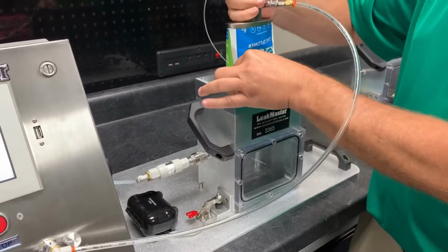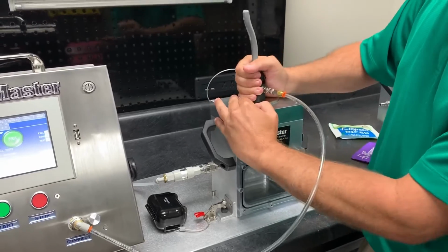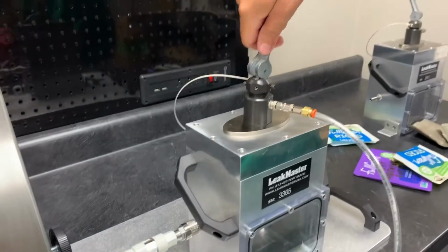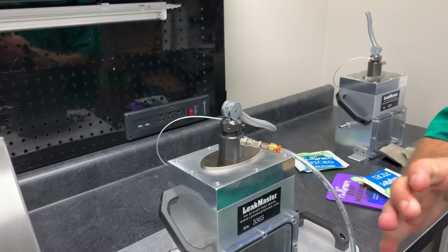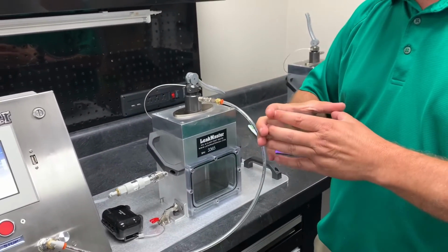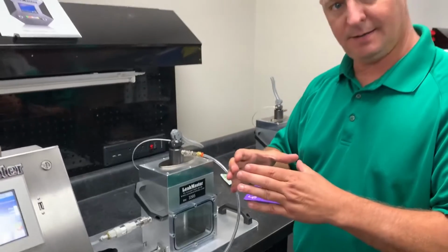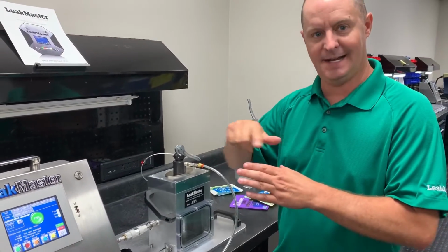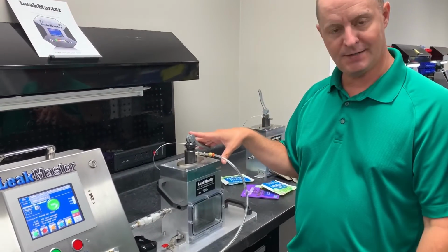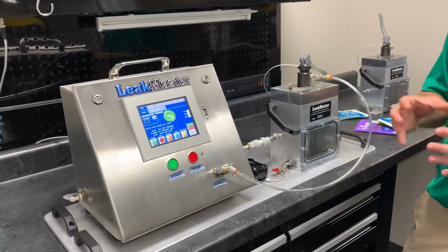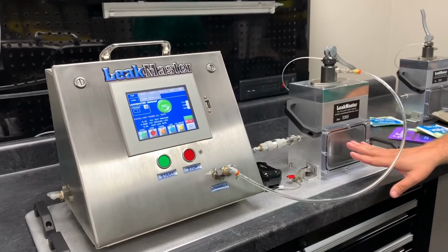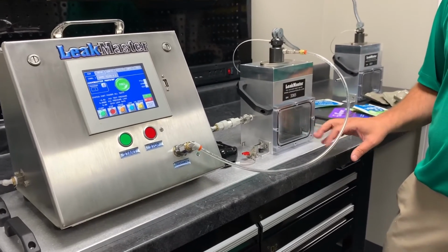So once we've got the part fixtured properly, this cam over seal is going to swell up that inside diameter and seal off the inside of the product while pressing it to the outside diameter seal. So at this point, it's ready to be tested. Now when I hit start, it's going to pressurize this bag. The bag's going to swell up. There's a little sight window here where we can see inside there.